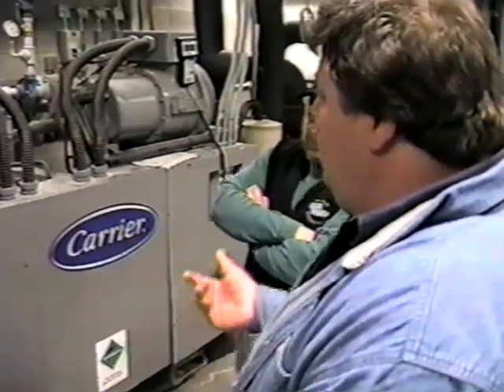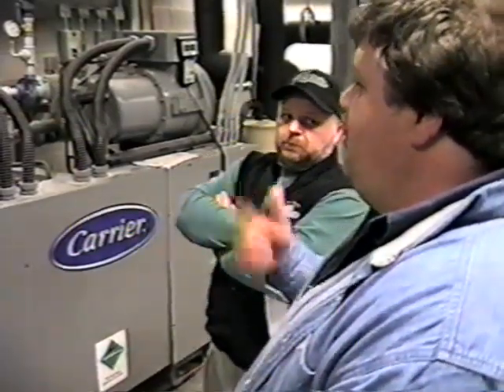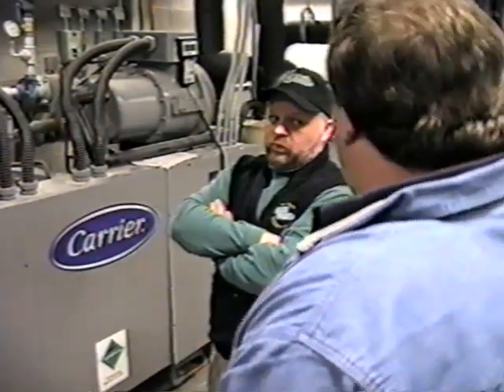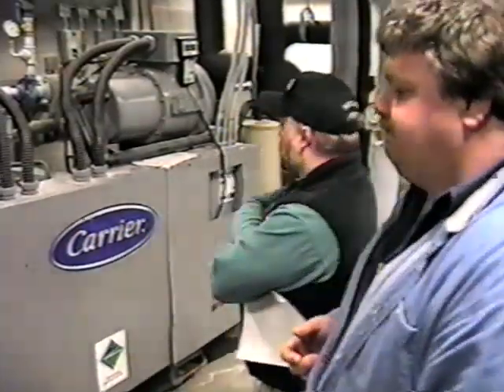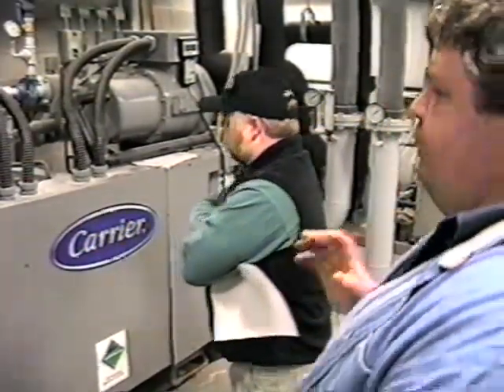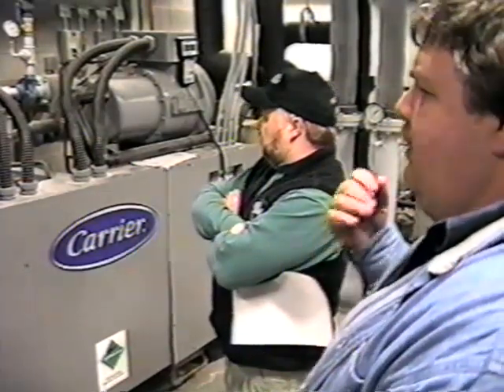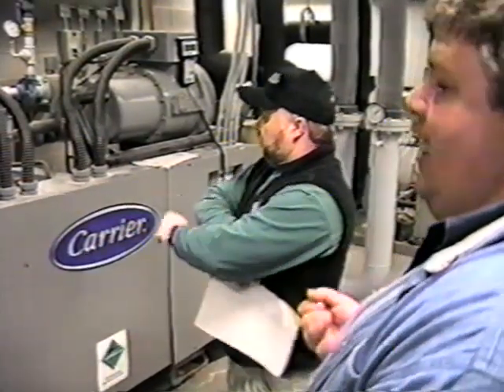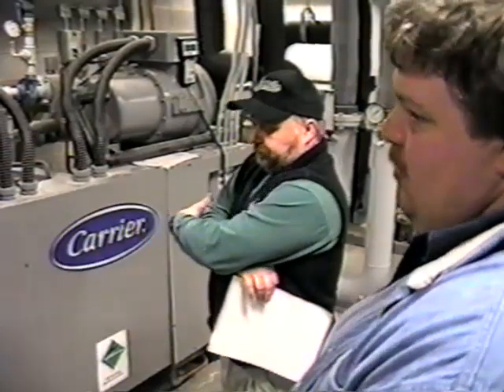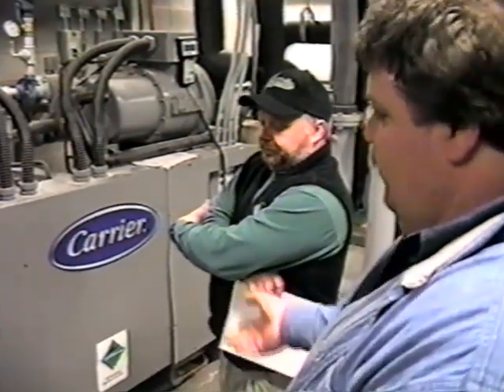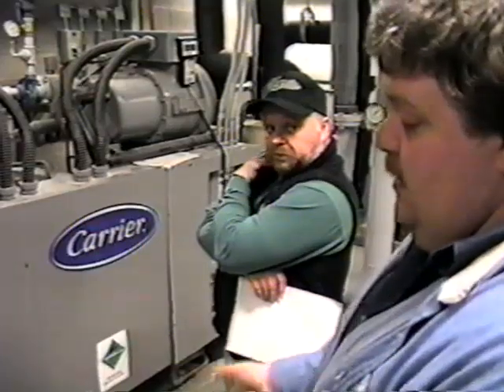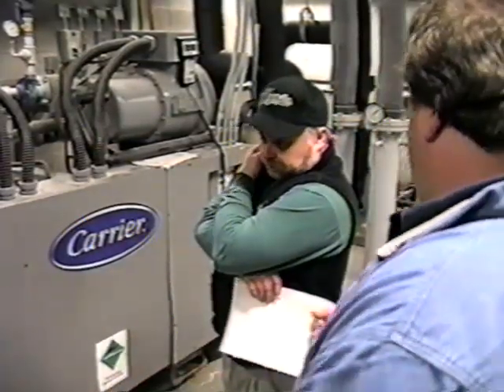And by doing that, you're also going to get used to the natural sounds in the room. Right. And 90% of the troubleshooting that you guys are going to do is going to be, I hear something funny. It's not so much the eyes. You should be looking at the sump and stuff like that, but it's more, do I hear something clanging or a different pitch from the compressor, something that's not usual in the room. Same as with the other side of the building. The other thing would be something on the floor that shouldn't be there. Water's okay, oil's not.